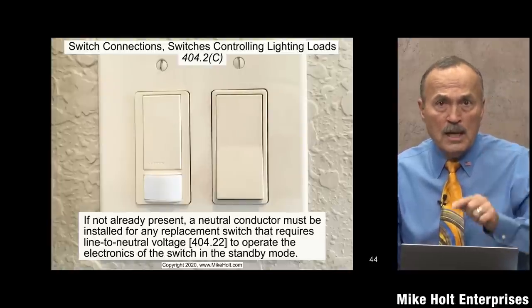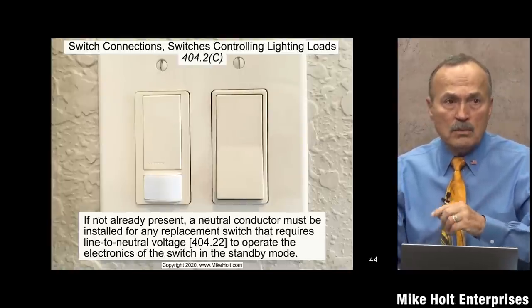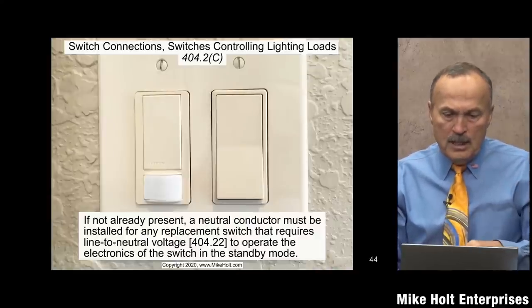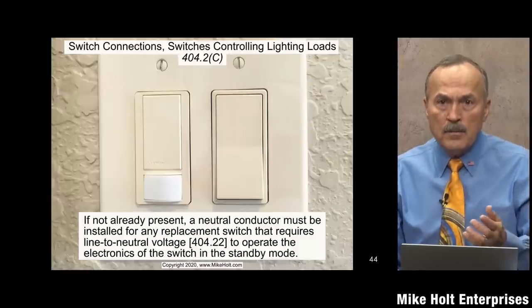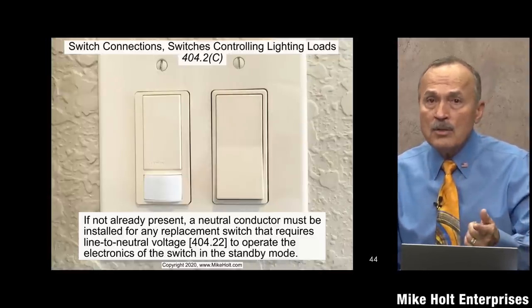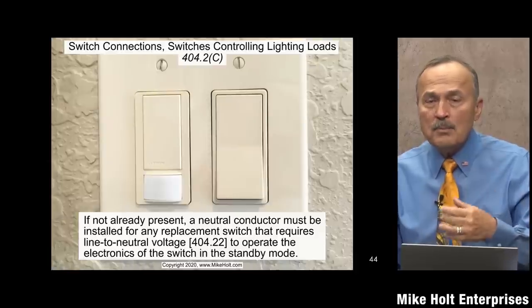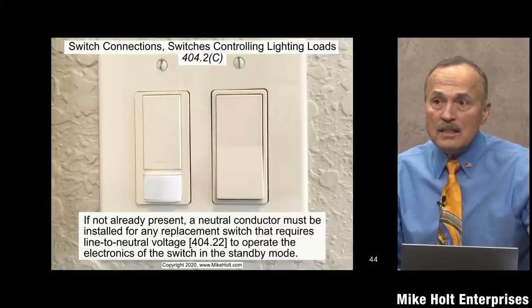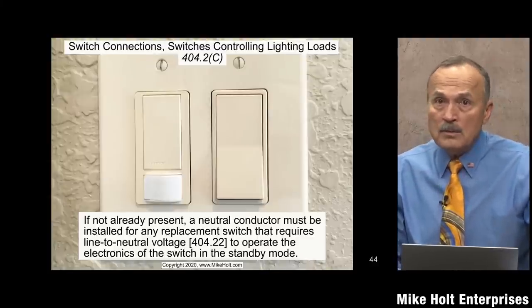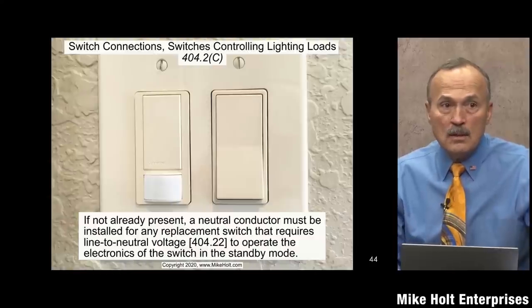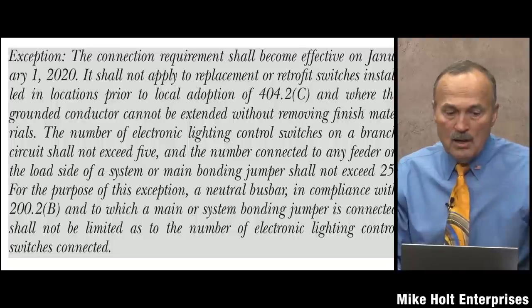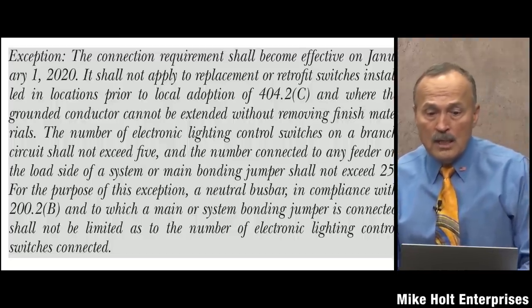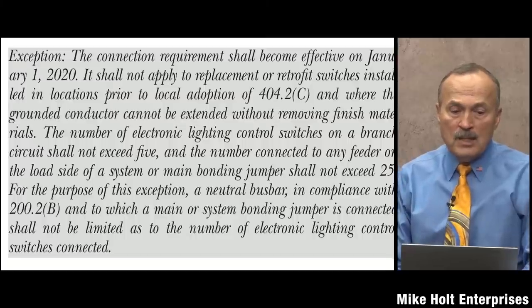The rule is: when installing an electronic switch, you need a neutral there; if no neutral is present, you must add one. The connection requirement for electronic lighting control switches became effective January 1, 2020 — this aligns with the 2020 NEC code cycle.